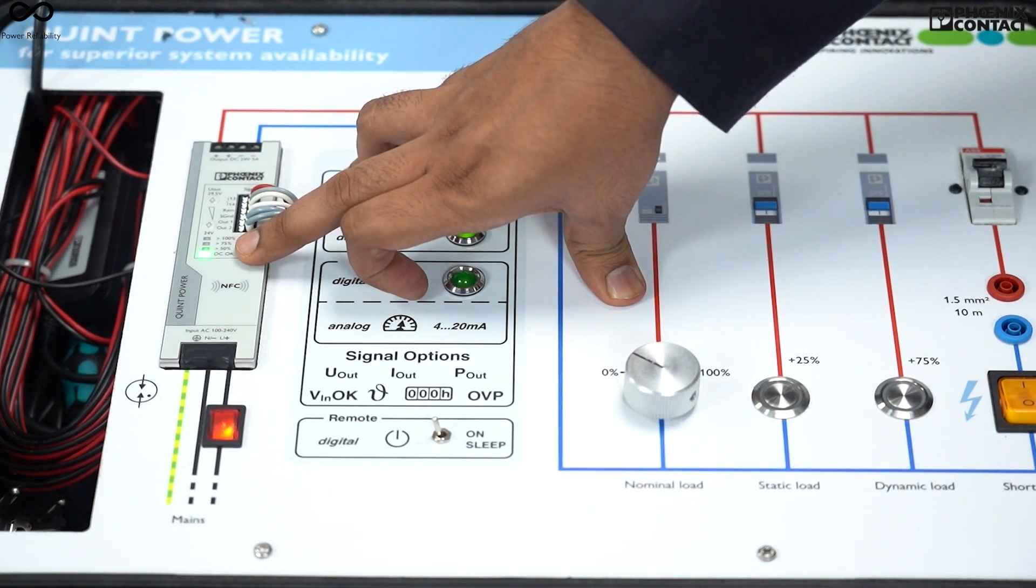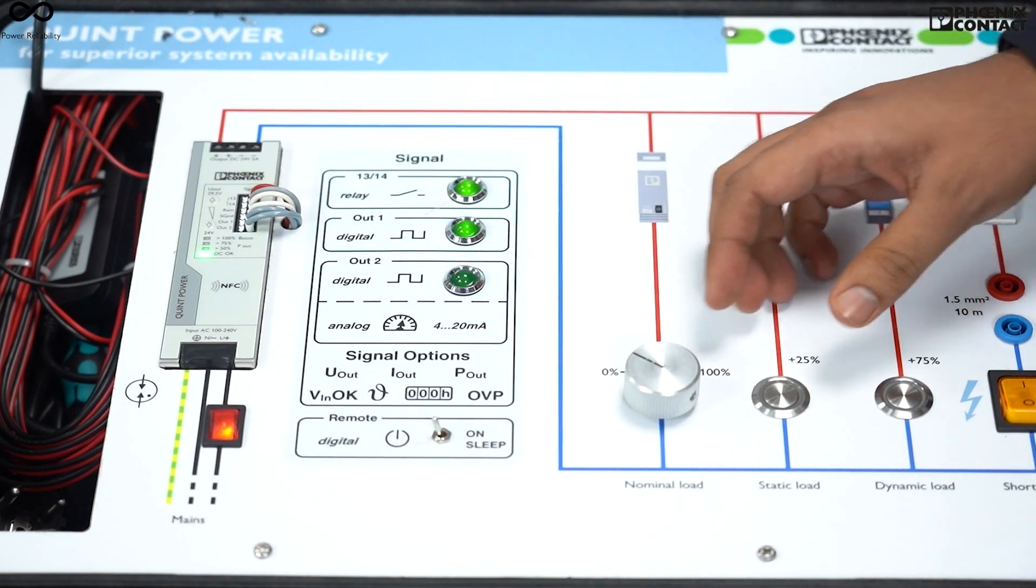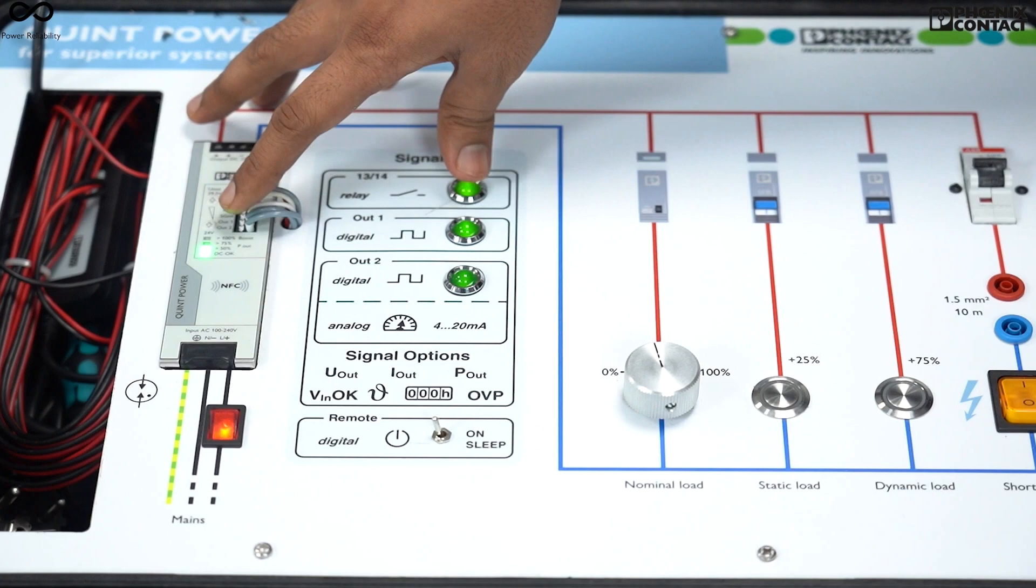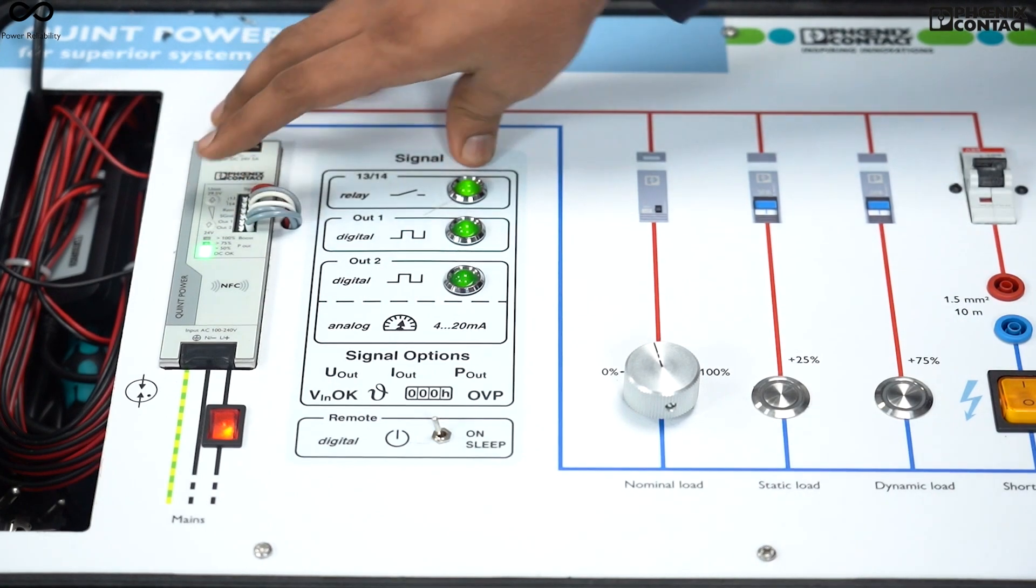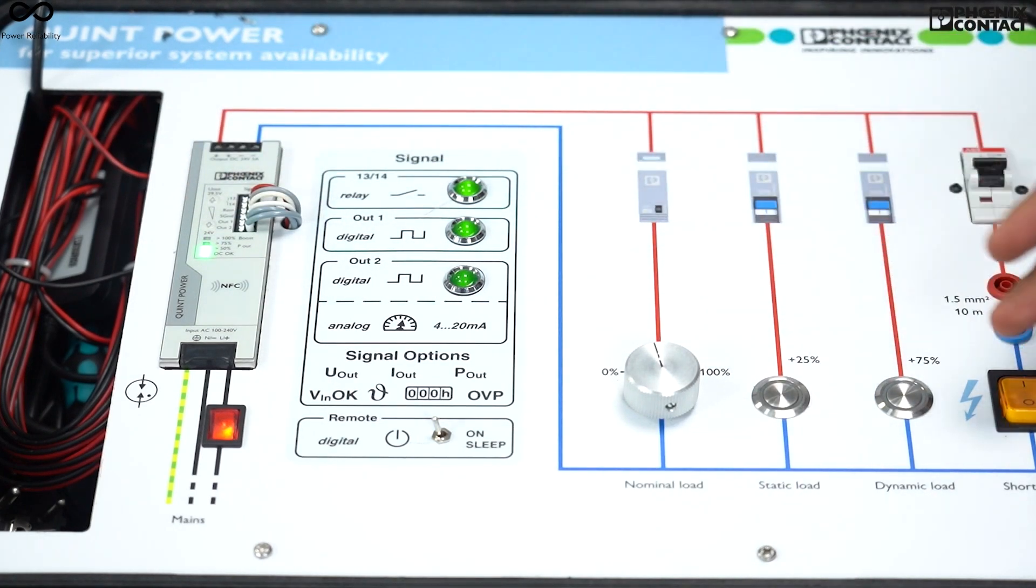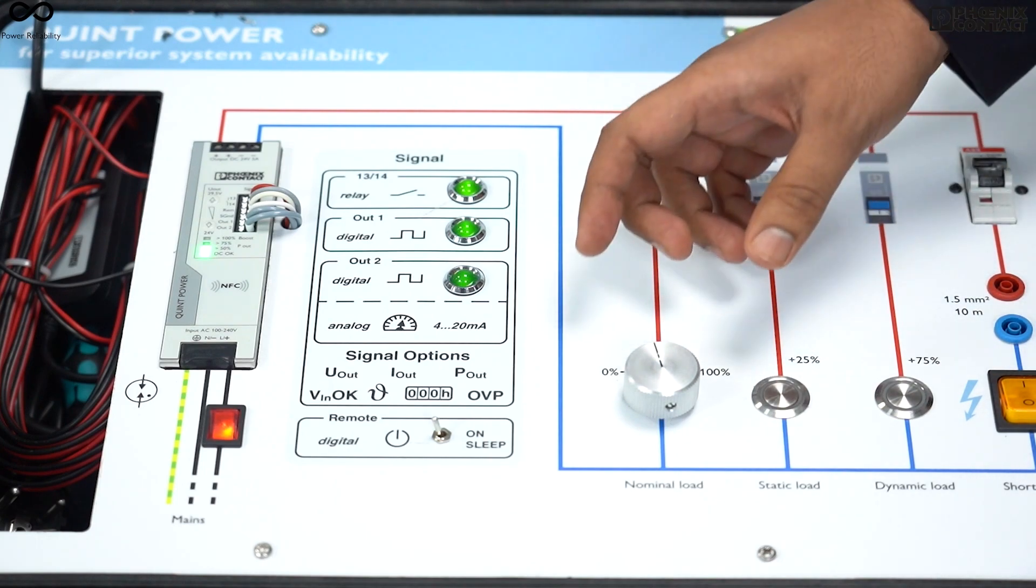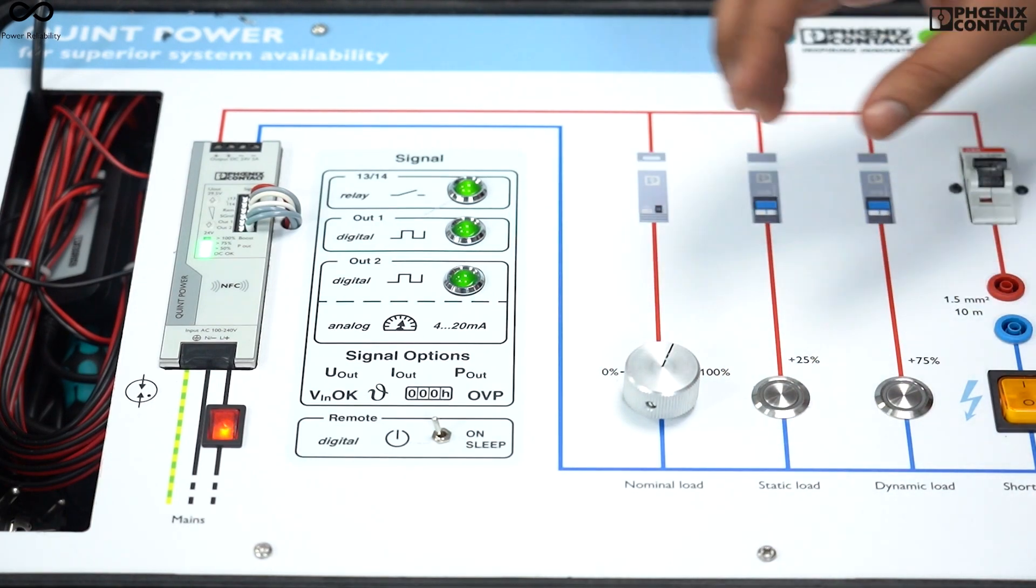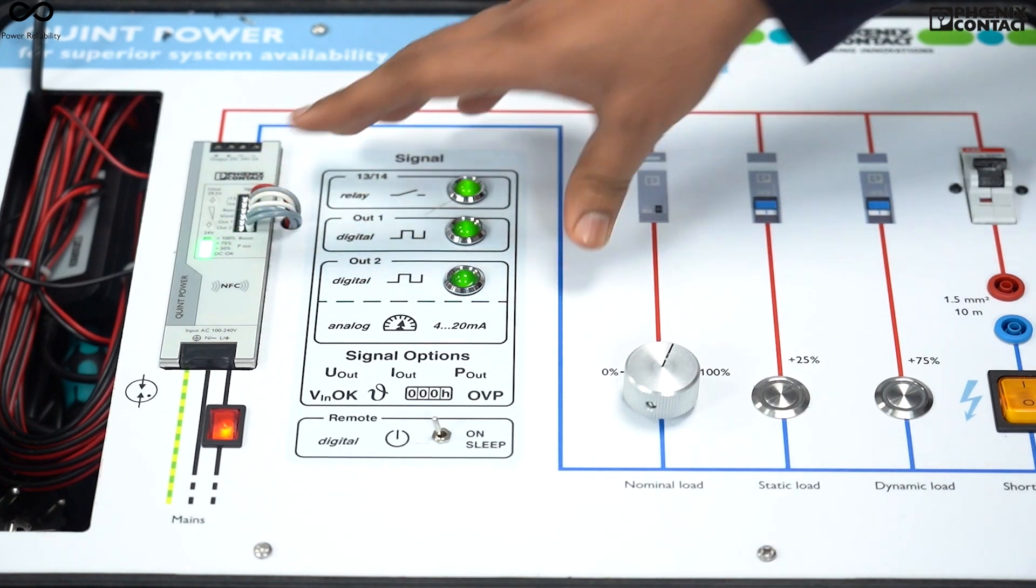Here you can see right now the power supply is on no load, so only DC OK LED is glowing. If I put 50 percent loading on the power supply, only the first LED starts glowing, which gives you the information that power supply is working up to 50 percent or less than 50 percent. Now again, if I increase the load like 70-75 percent, the third LED starts glowing.